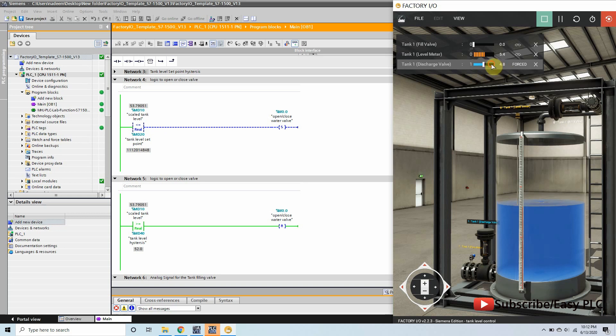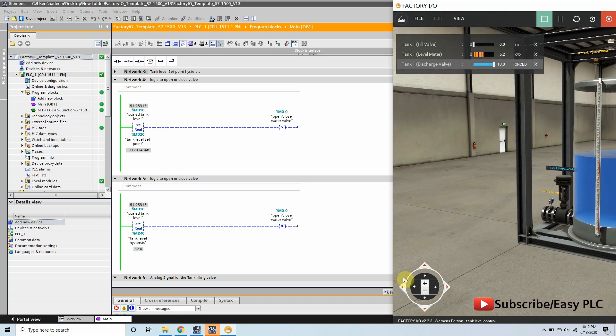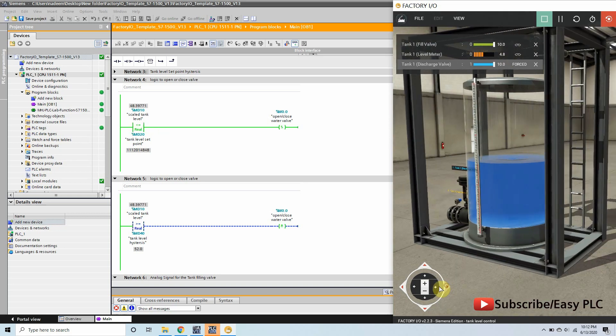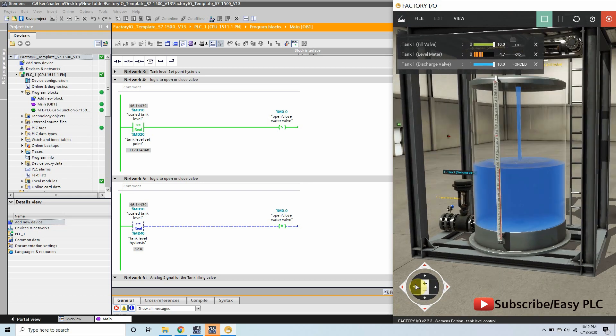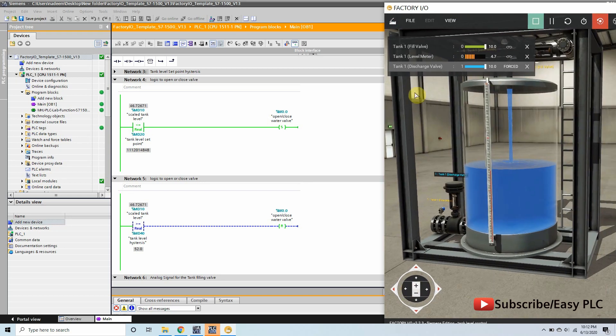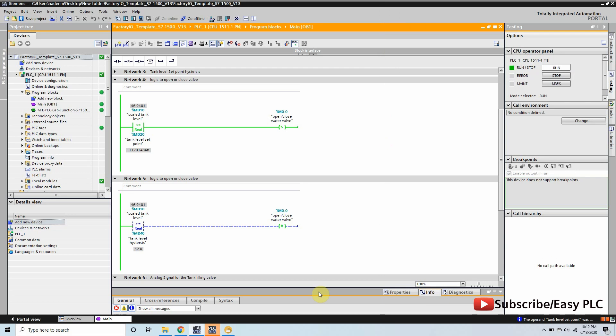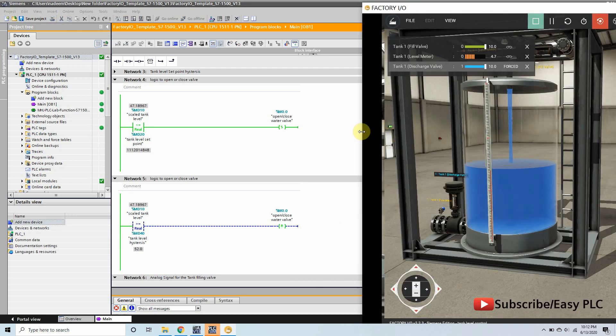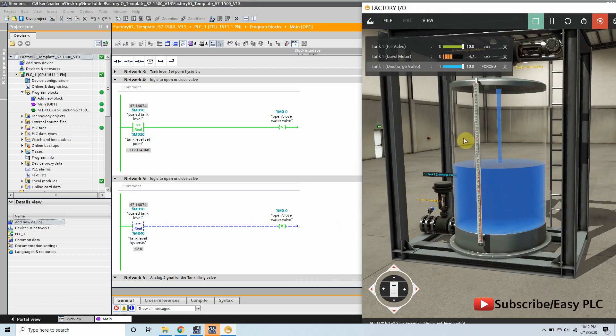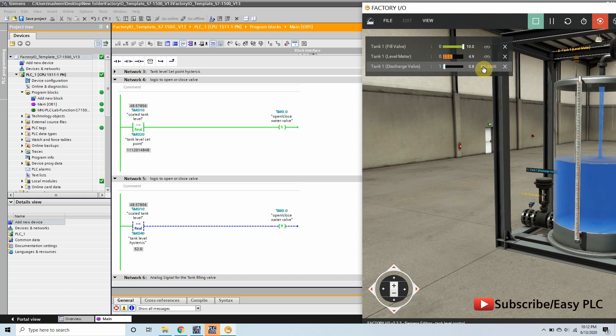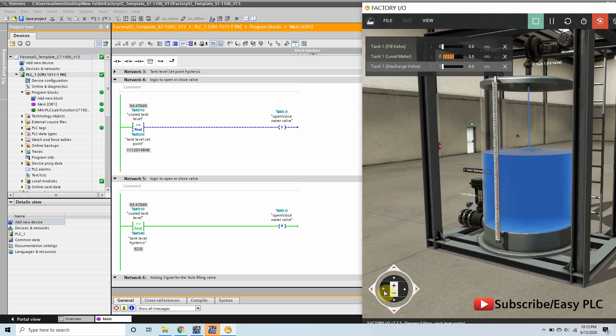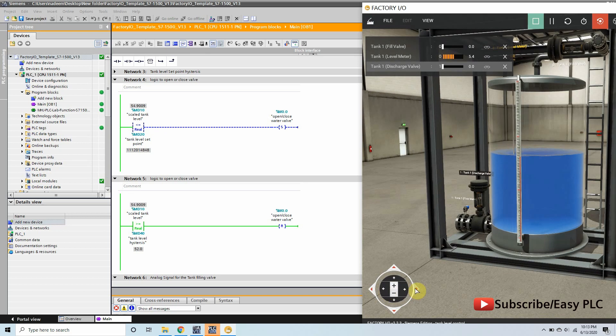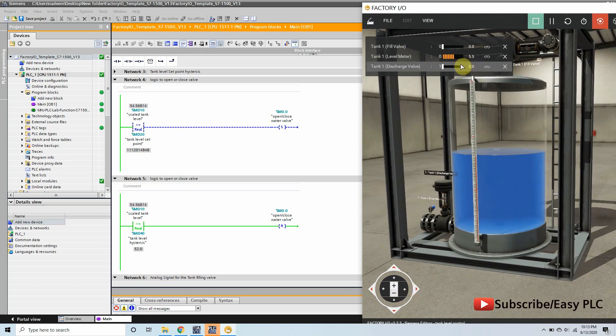Let's drain the tank so that the filling cycle will start again. You will see that the filling valve is open again. The filling valve opens once the level drops below 50 liters and will stop once the level has reached 52 liters. This filling and stopping cycle repeats consistently as the tank drains and refills.